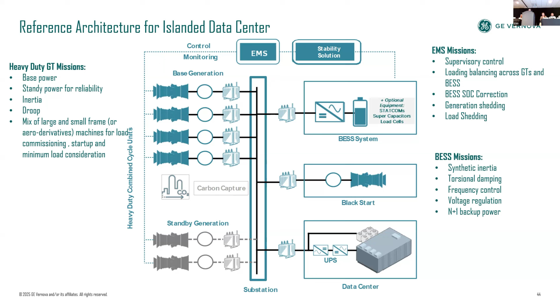Now, one of the aspects that is important to the islanded system is the frequency. We all know that whenever there is an imbalance between generation and load, it will cause the frequency to vary, or the speed to vary. And this is particularly important because of the large transient caused by the training of the AI load. As described earlier, when the training first starts, it appears as a large step, and that step can vary anywhere from 25 to 40 or 50% of the rated load.